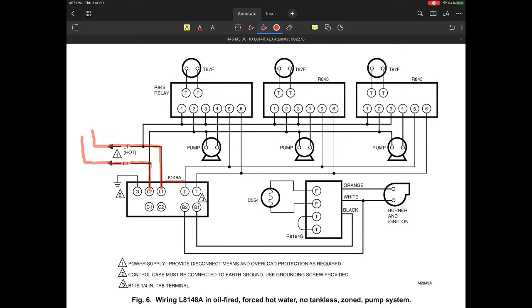So in this example, they're taking line 1 and they're feeding L1. They're taking line 2 and they're feeding L2. So this is powering up the Aquastat relay, which is the L8148A. We also are powering up terminal 1 and terminal 3 on every one of these relays. Now, terminal 1 in this particular case is really on these R845 relays, zoning, they're like an individual zone pump controller. What they're doing is they're powering up a transformer, which is how this is able to function. So that's the function of that.